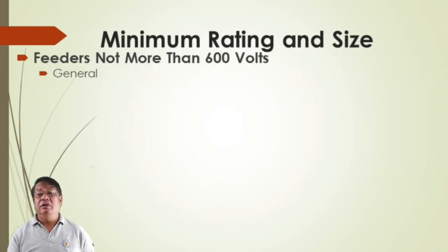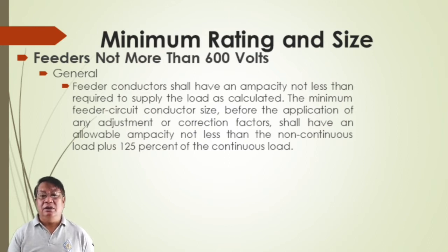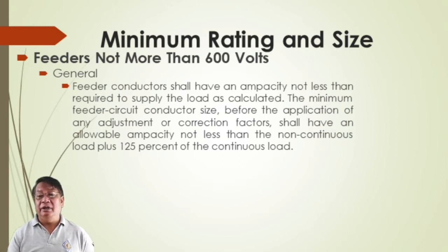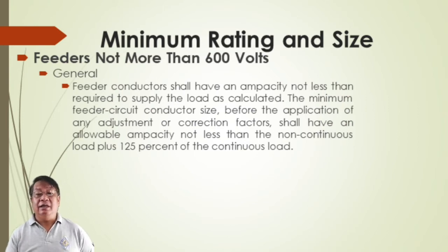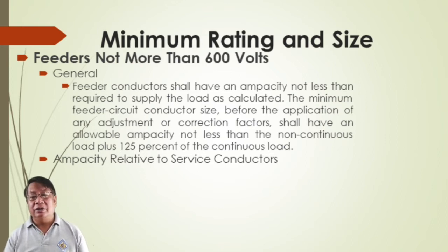Not more than 600 volts minimum rating on sizes of the feeder or conductor used to supply the branch circuit. It shall have an ampacity not less than required to supply the load as calculated. The minimum feeder circuit conductor size allowable ampacity is not less than the non-continuous load plus 125% of the continuous load. That is the general rating for not more than 600 volts systems.